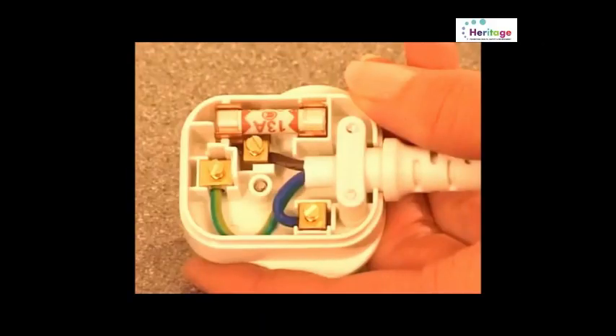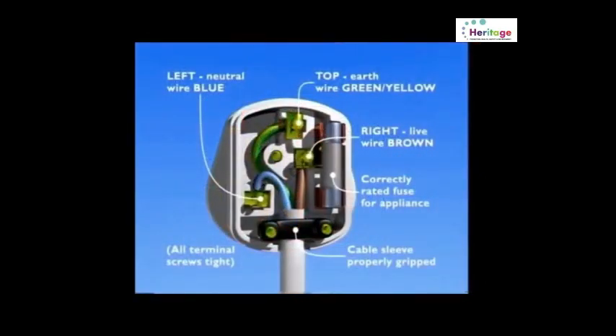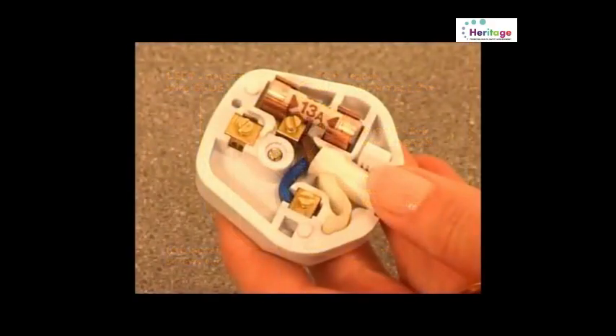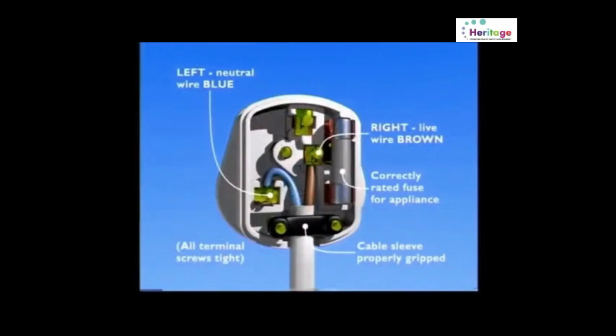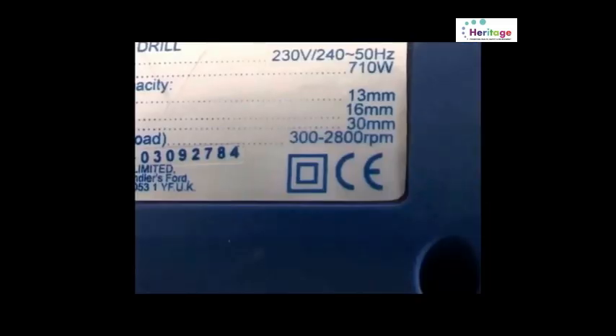A Class 1 appliance is an earthed appliance. Open the plug to determine if the appliance has 3 wires. A Class 2 appliance has no earth wire. Again, open the plug to determine that there are only 2 wires. A double insulated appliance is marked with this symbol and must be tested in the same way as a Class 2 appliance.